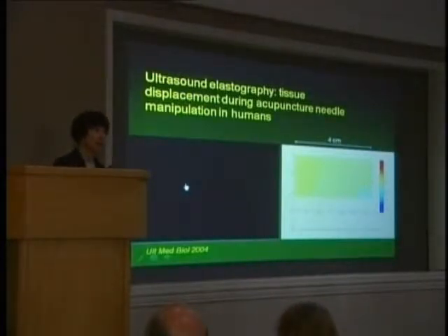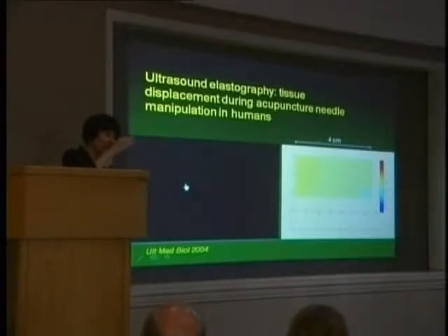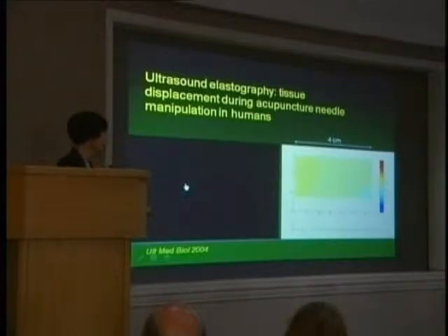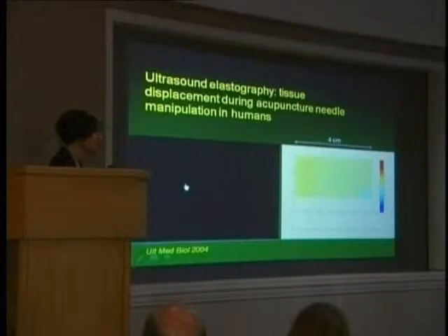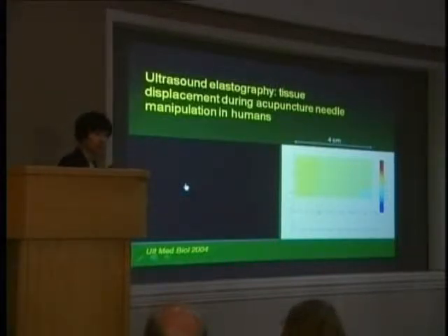What we do then is we use a technique called cross-correlation, which analyzes the image by correlating the pixel movement from one image to the next. It generates a series of color images where red indicates movement upwards towards the skin, and blue indicates movement downwards, away from the skin. And what you're going to see is waves of color that move across the image, corresponding to the B-scan ultrasound I just showed you.